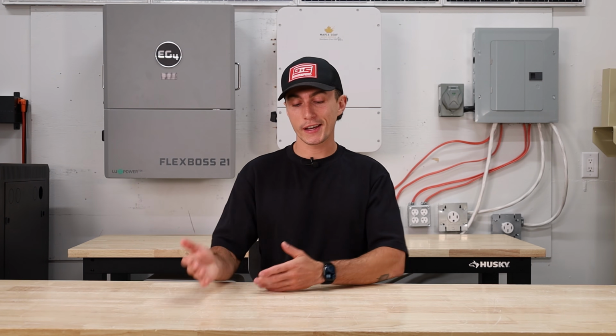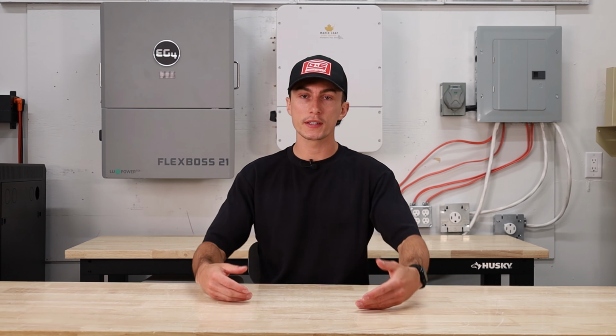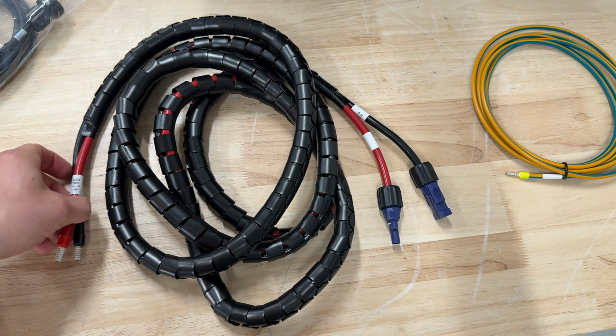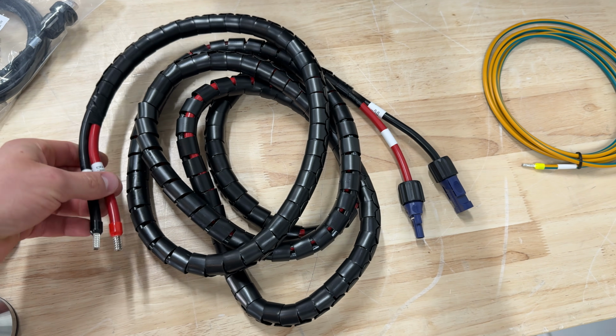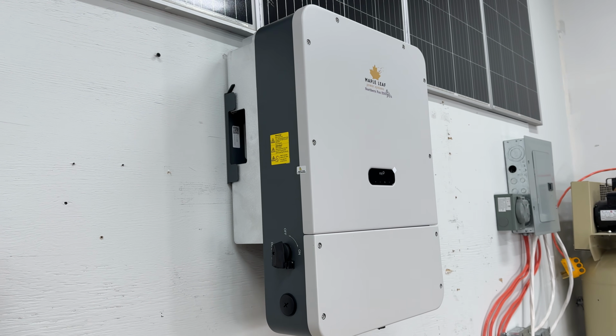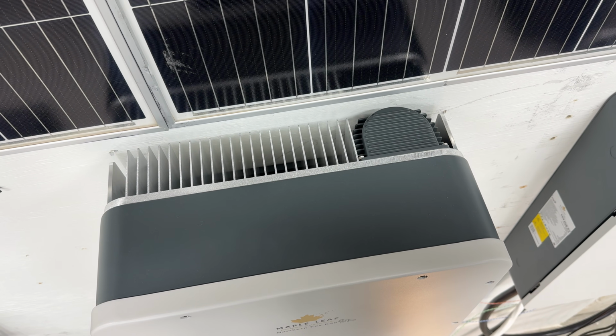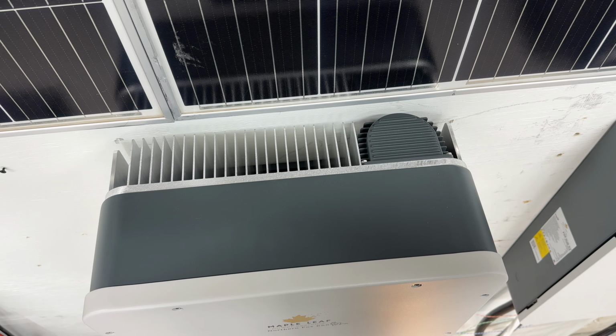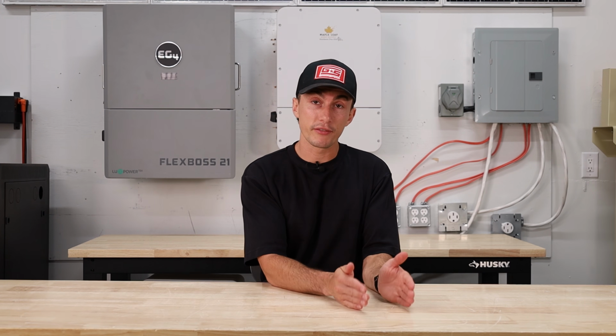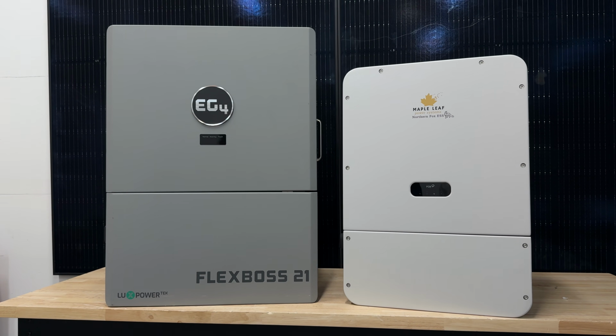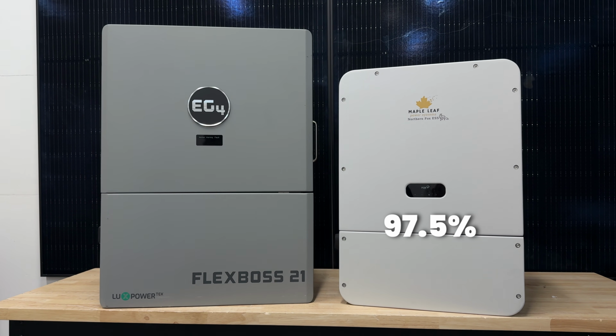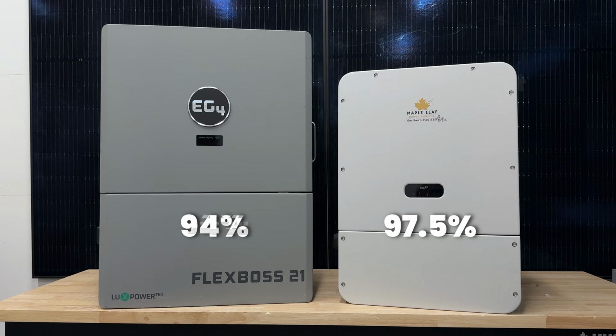When it comes to the efficiency of the high voltage stuff, we've already hit a ton of these points. You have your smaller wire, higher voltage, lower amperage. It's way more efficient to send power through it. Your inverter does not have fans, so there's more efficiency gained from the inverter not running your fans. But for numbers' sake, the efficiency rating on this Fox ESS system is 97.5%, whereas the EG4 efficiency rating is about 94%.